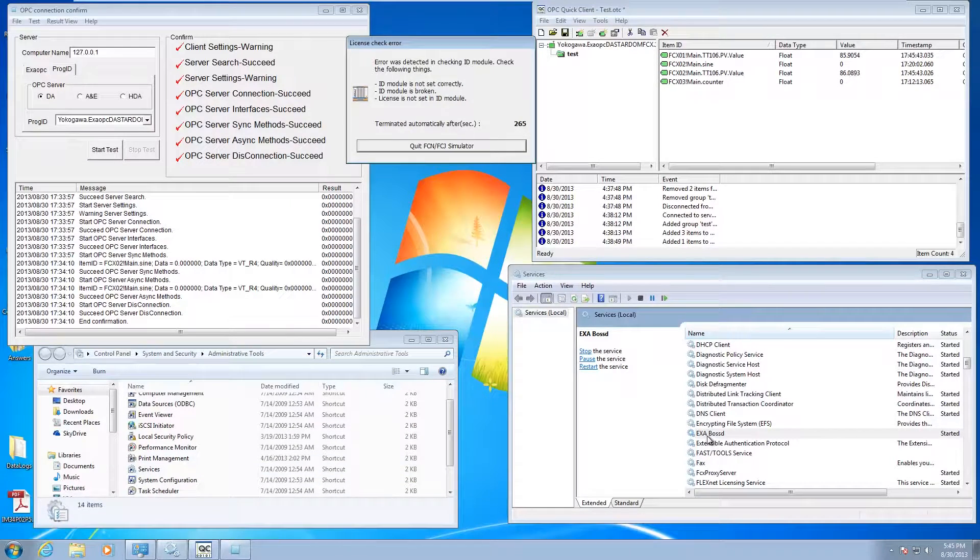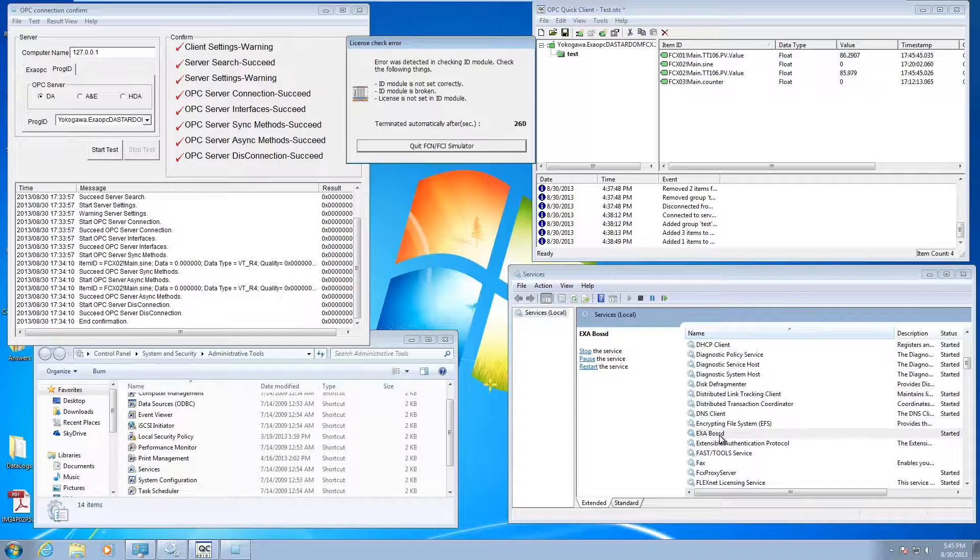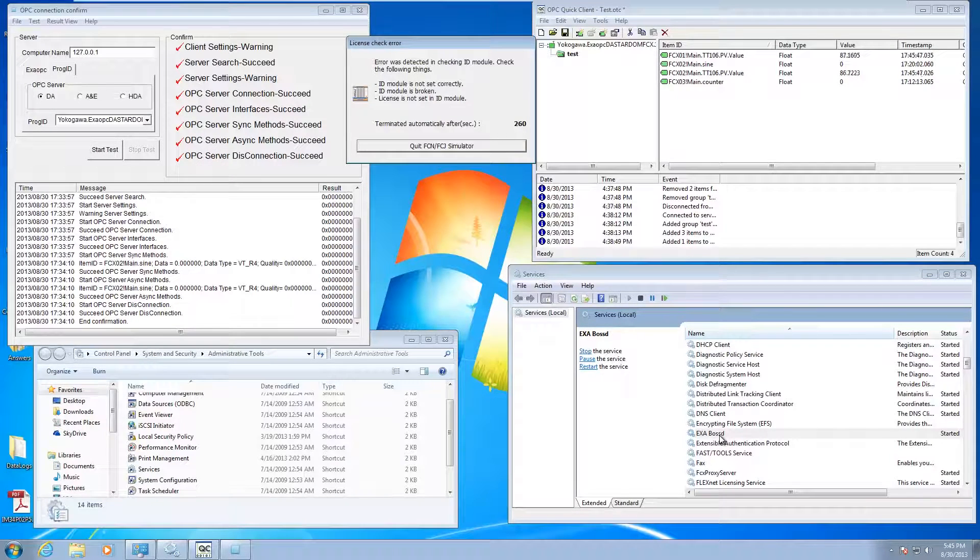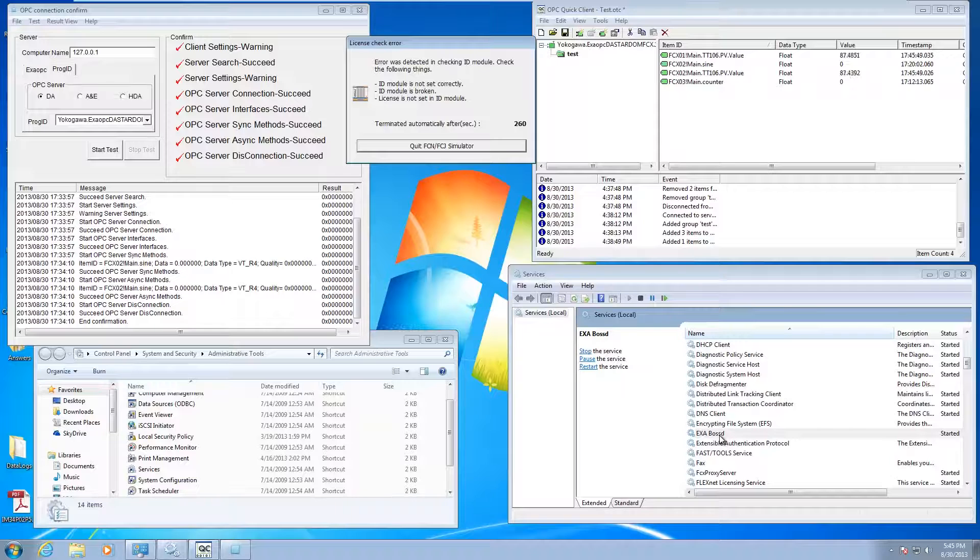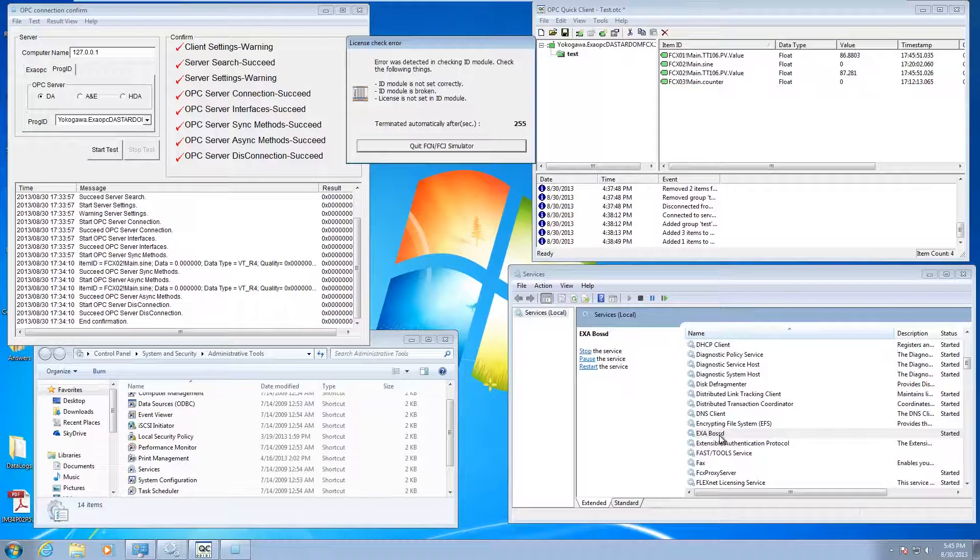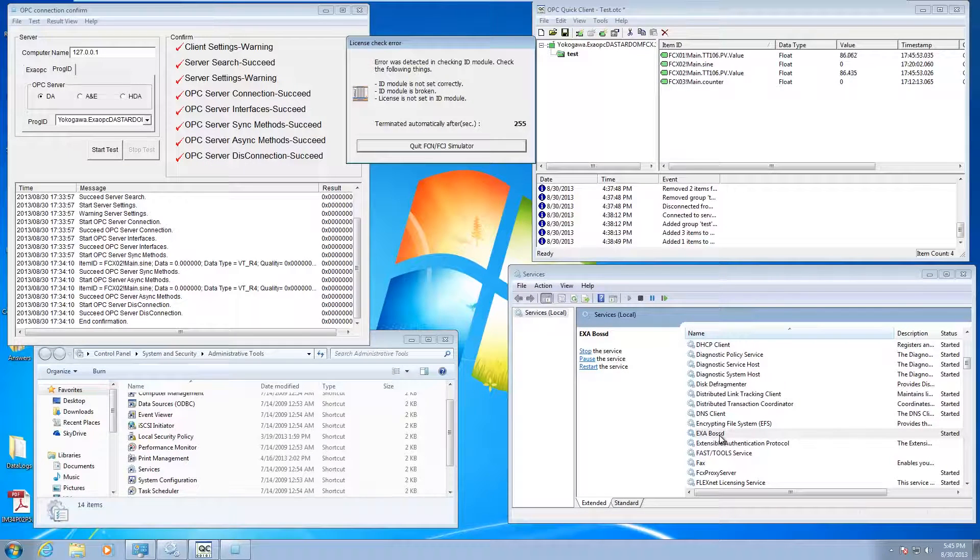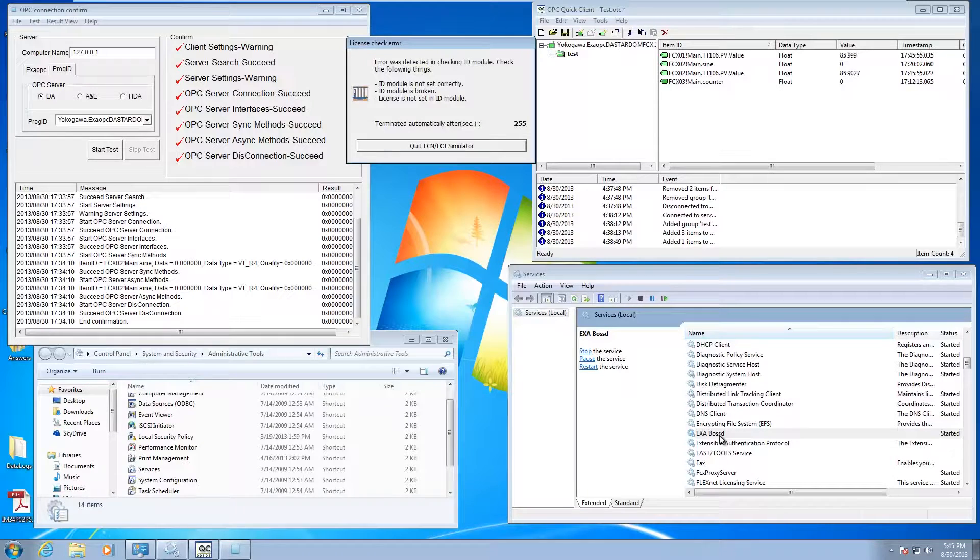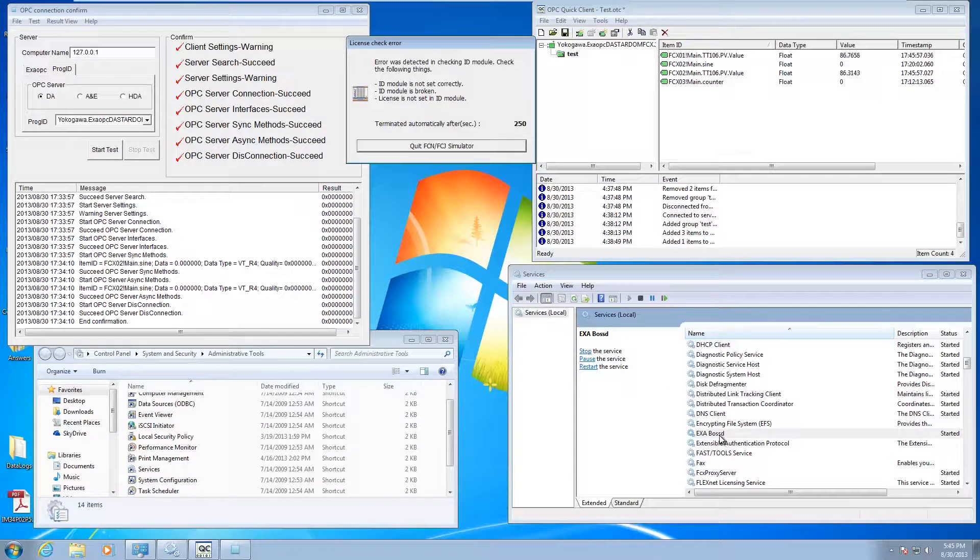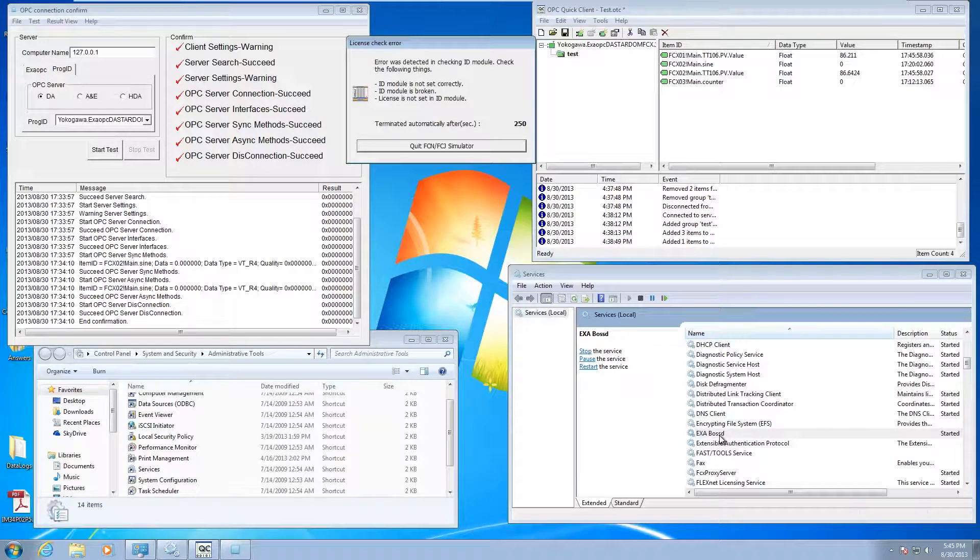There's a service called EXABroad. If you stop this and then restart it, it'll load in those configuration files. That'll stop your OPC connection, load in the new IP addresses, and then you should be good to go.